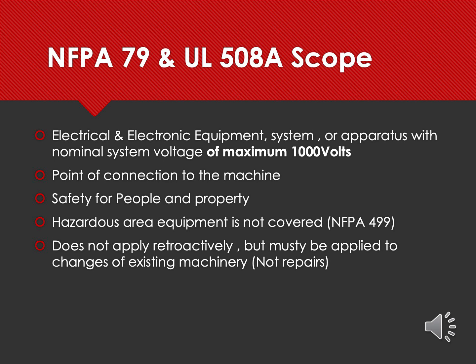Because both the machine supply and control panel supply generally involve the same supply terminals, it's also possible that both standards apply to the control panels. Whenever in doubt, make sure you agree in advance with the end user which standard is relevant to them. In practice, however, this cannot always be clarified beforehand. In this case, it's almost always recommended to comply with both standards. This does not pose a major problem because the two standards are not contradictory and most requirements are similar or identical. In some cases, one standard allows less room for interpretation of requirements than the other. In this case, it's always recommended to comply with the more stringent requirement.